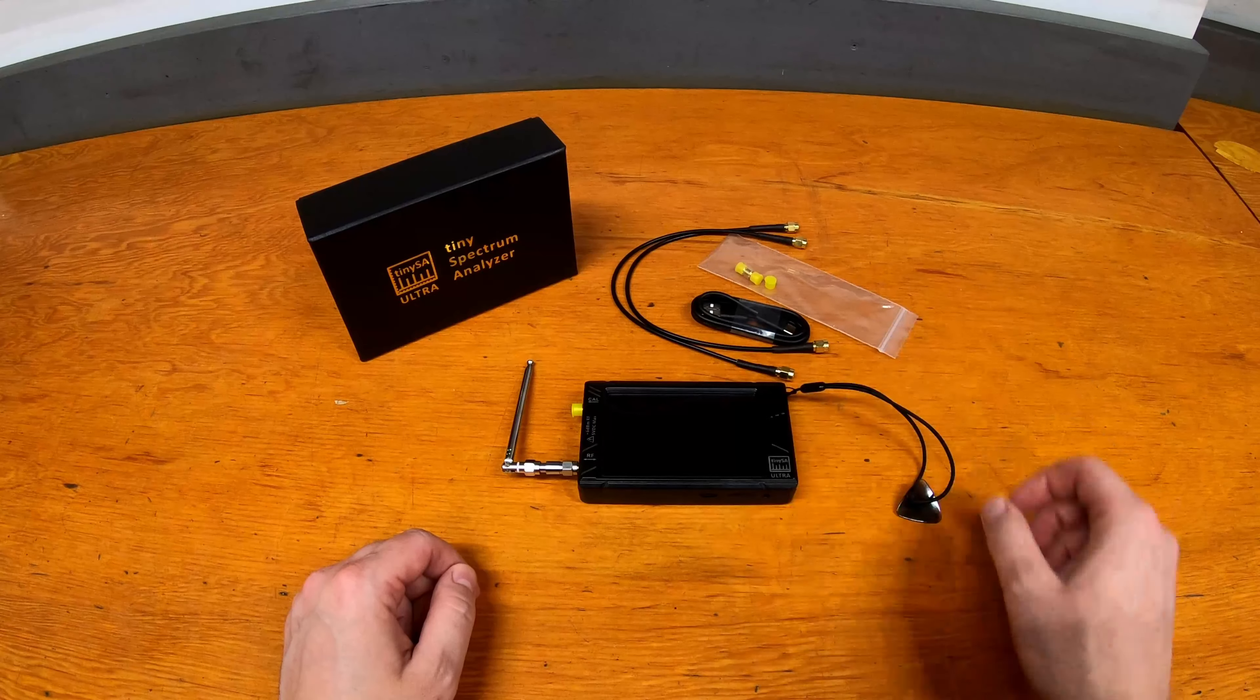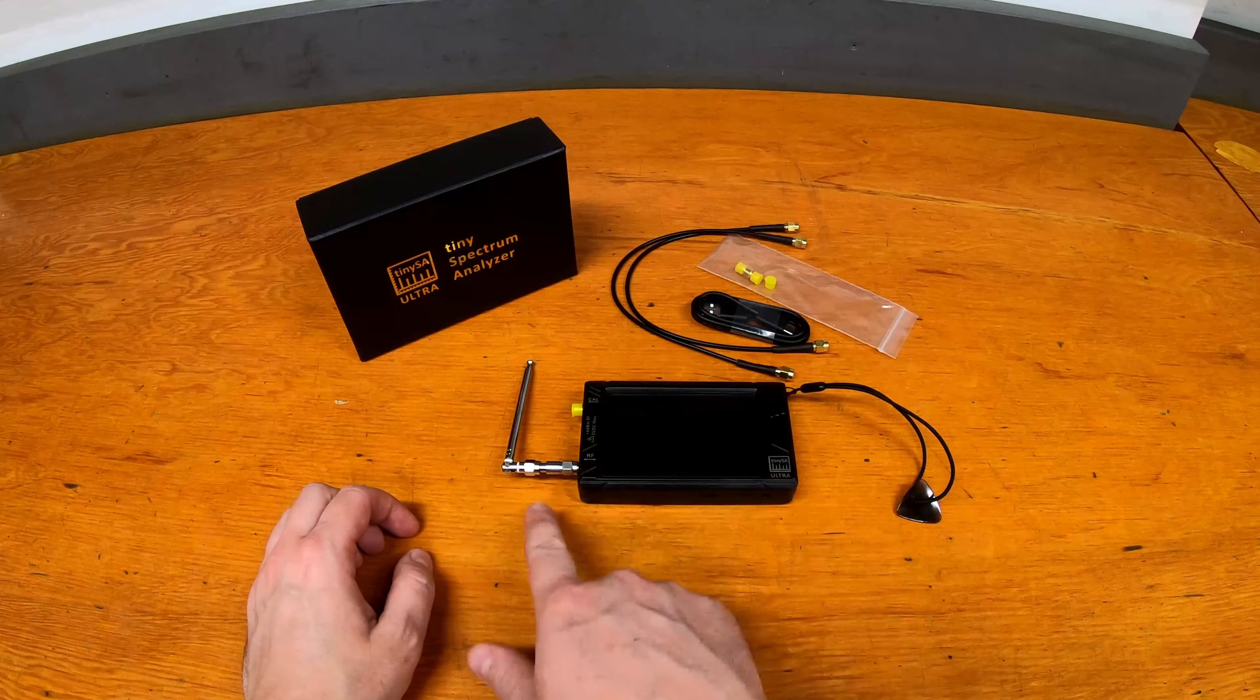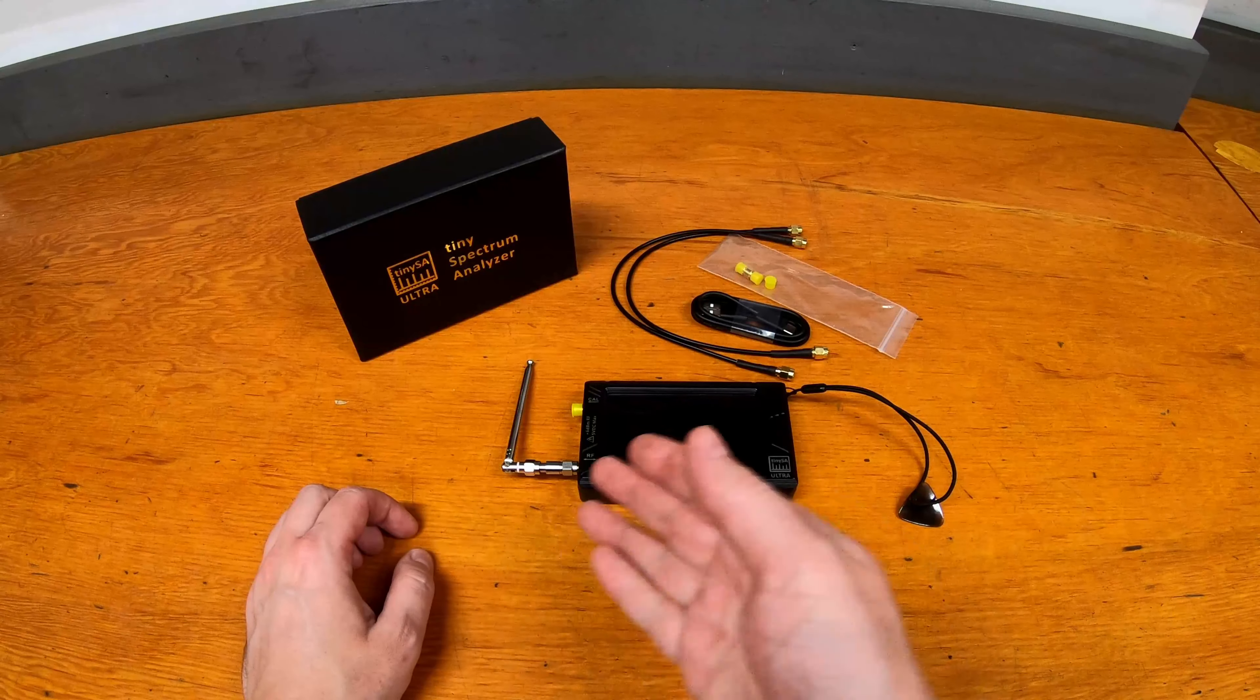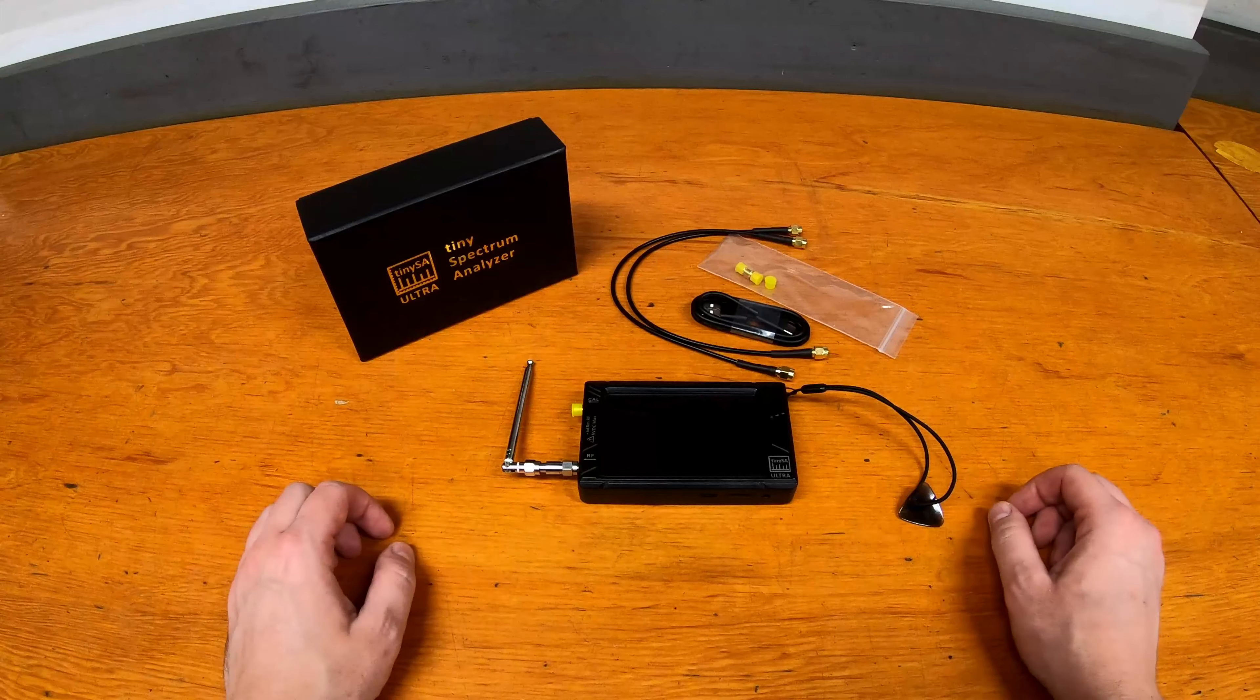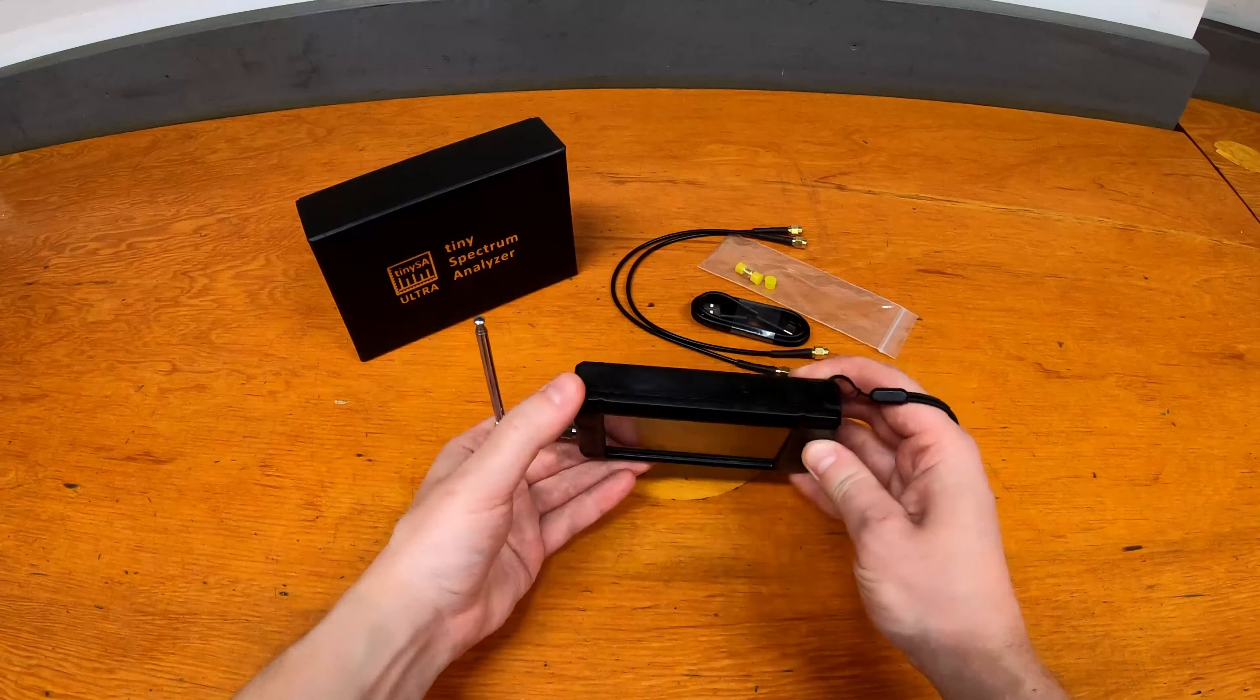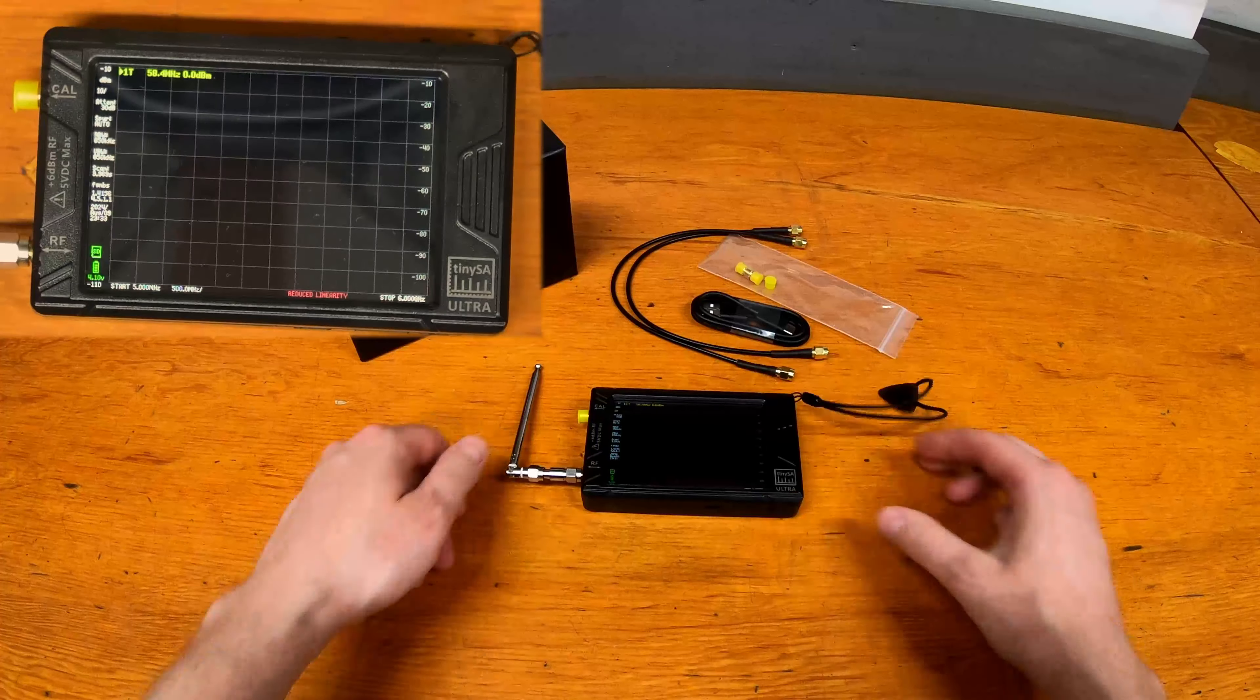Or you can use these to hook up to a radio or something if you have the right adapters. Of course, keeping in mind that max level that you don't want to go too high when you have a direct coupling. So putting like 5 watts into that with a fairly powerful handheld radio could actually break the unit. And then just the only other features, there's a scroll toggle wheel on the top and the power switch. So let's hit the power switch and start it up.